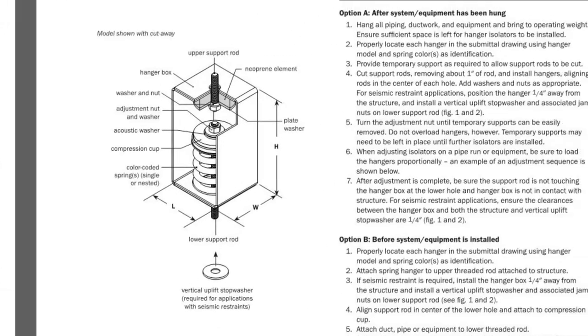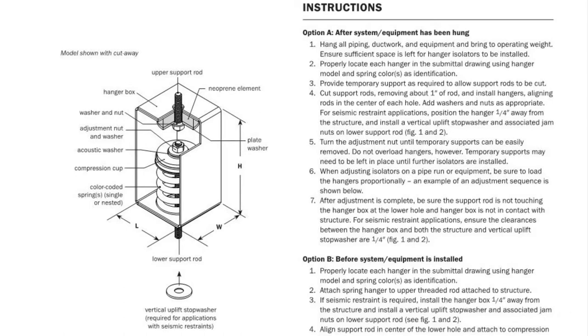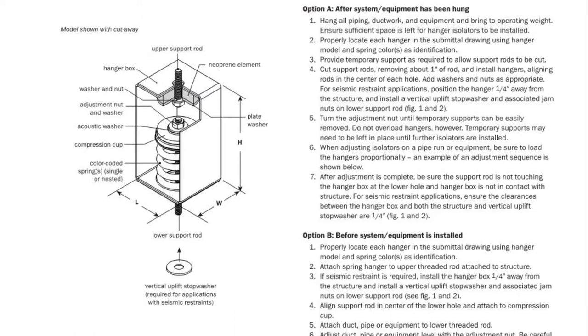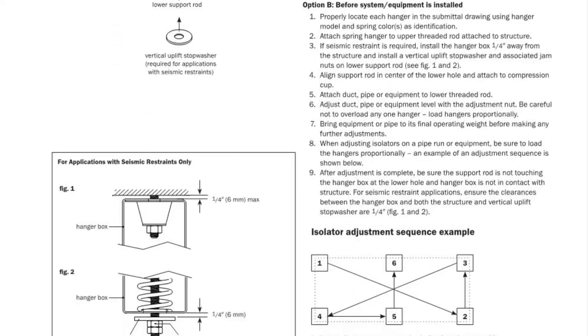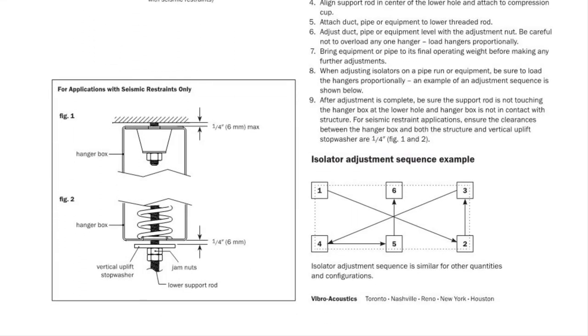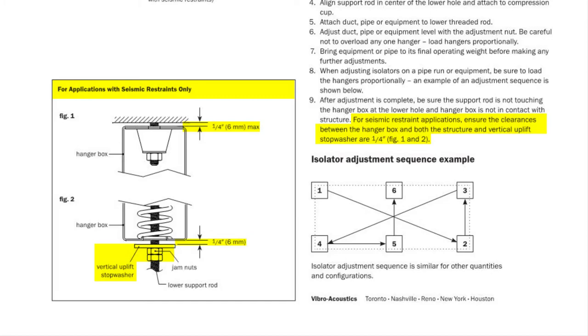Taking a look at the SH-R installation instructions, there is little difference from the SH instructions except that the top of the hanger box cannot be touching the supporting structure, and when installed along with seismic restraints, the hanger box must be installed a quarter inch away from supporting structure so that it acts as a vertical limit stop. Uplift stop washers must also be installed as shown.